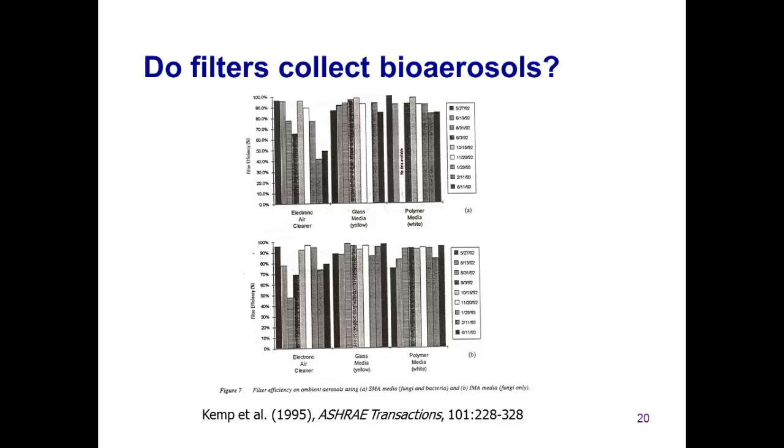We can ask the question, do filters collect bioaerosols? Published research indicates that they collect bioaerosols just fine. Almost 20 years ago, Kemp and co-authors showed that filters collected particles with high efficiency over time. The data in these figures were collected over a period of more than a year for two different types of filter media, a fiberglass media and a polymer fiber media. These filters collected particles with at least 80% efficiency over the entire study, both for fungi and for bacteria.